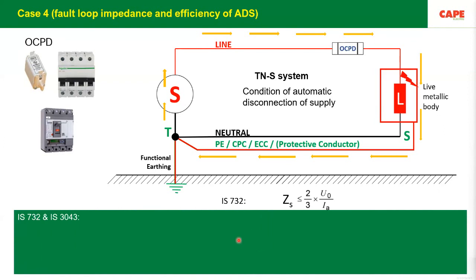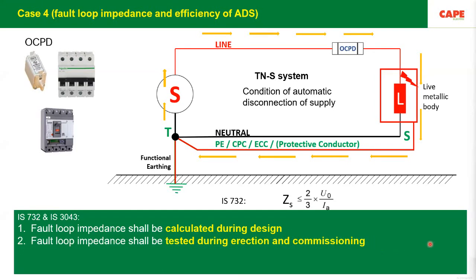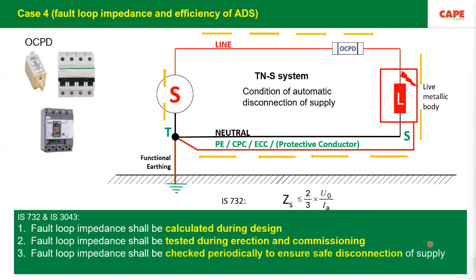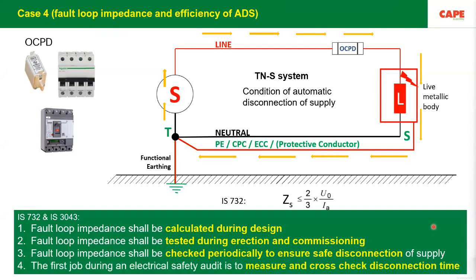Now, the code of practices such as IS 3043, which is not a new code of practice. IS 3043, the first standard came during, I think, 1965 or so. The standard has written very clearly that the fault loop impedance shall be calculated during the design. Fault loop impedance shall be tested during erection and commissioning. Fault loop impedance shall be checked periodically to ensure safety of disconnection of supply. And the first job of the electrical safety auditor is to check this particular parameter.